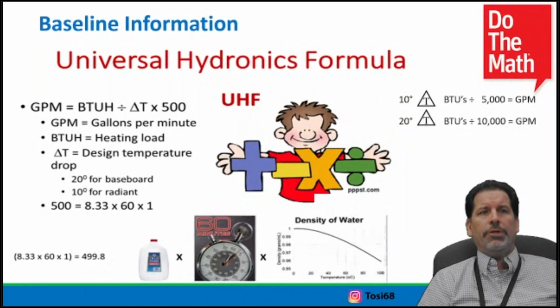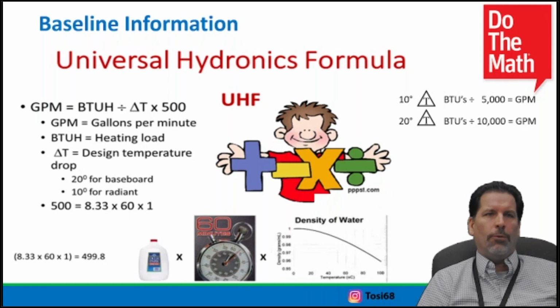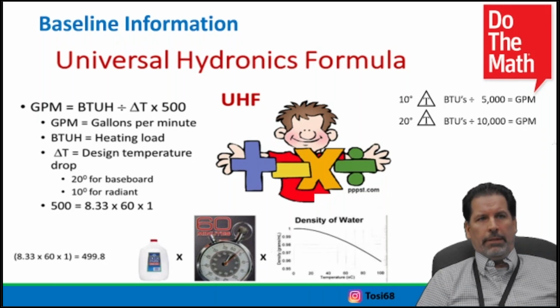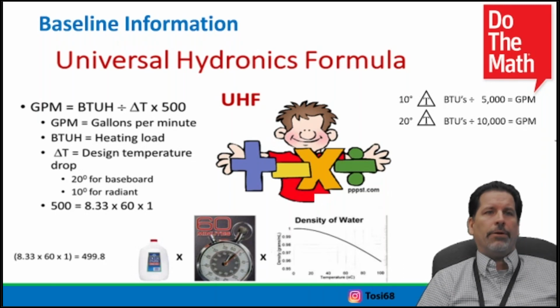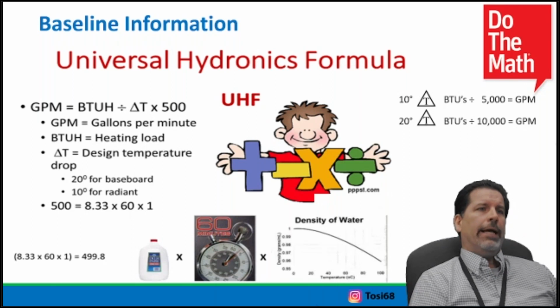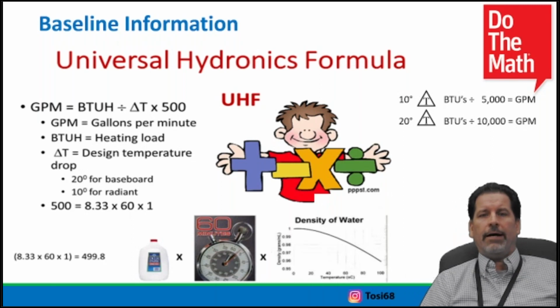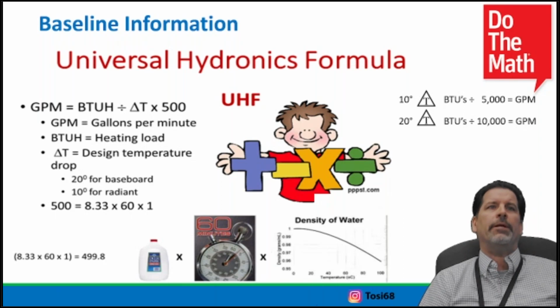And that's using a medium of water, using the 60 minutes in an hour, and the density and specific gravity of water is where we're starting. Pure water, we do different things with other fluids like glycol. So 8.33 is the weight of a gallon of water, 60 minutes in an hour, times 1 for the density of water where everything starts. Water starts at 1, and as we change the fluid, whatever it may be, it will derive off of 1. So 8.33 times 60 times 1, 499.8. We round it up, keep things simple.